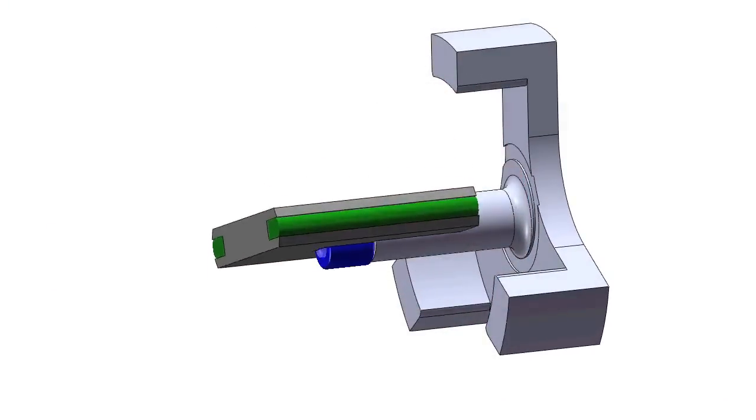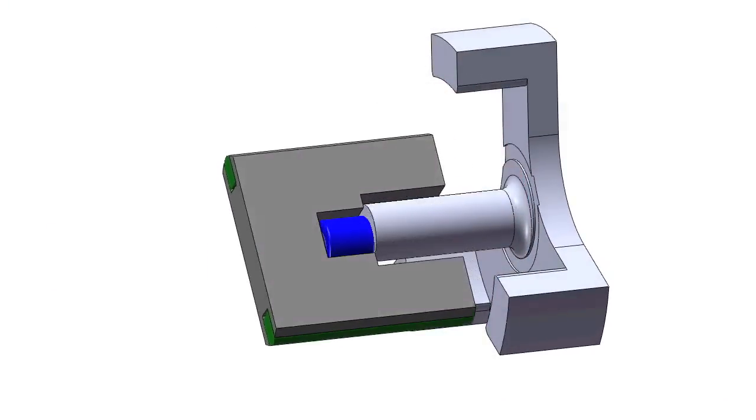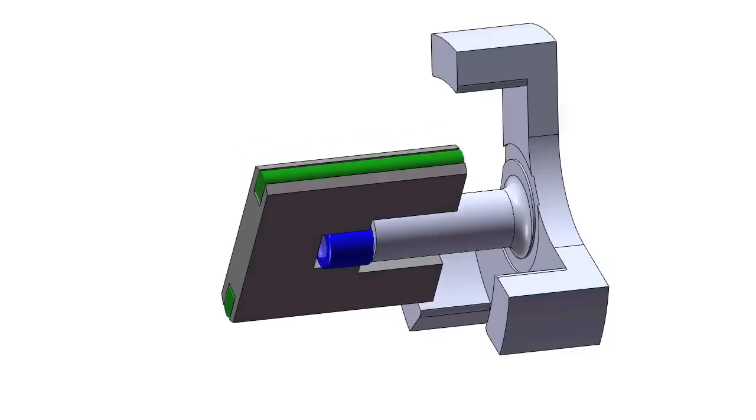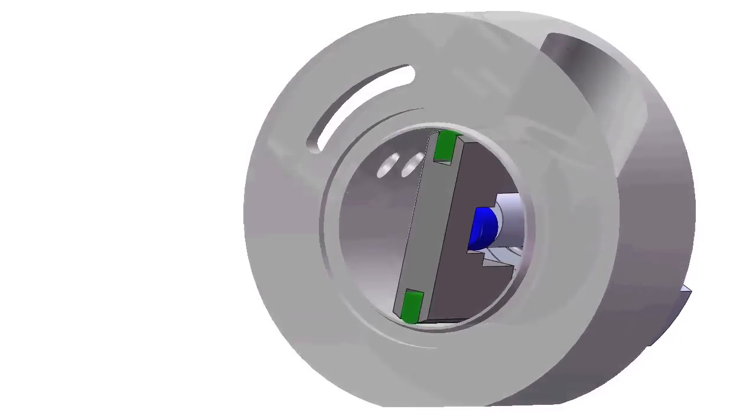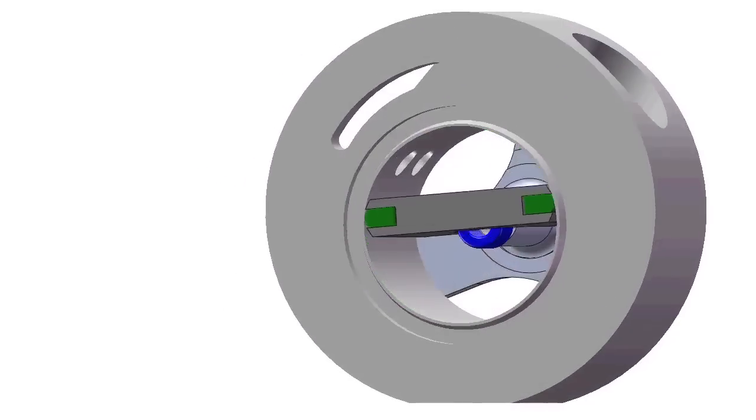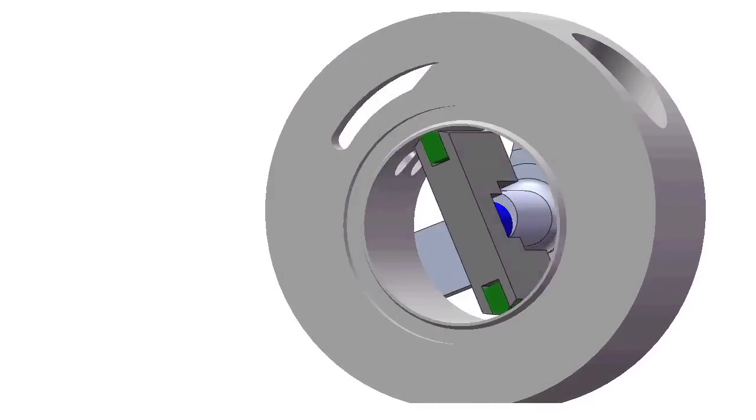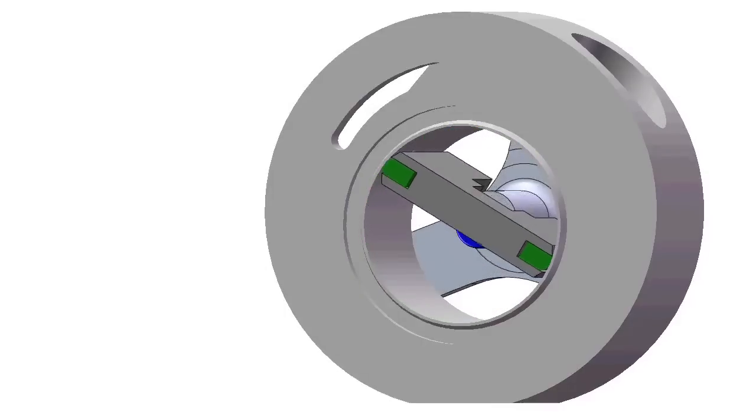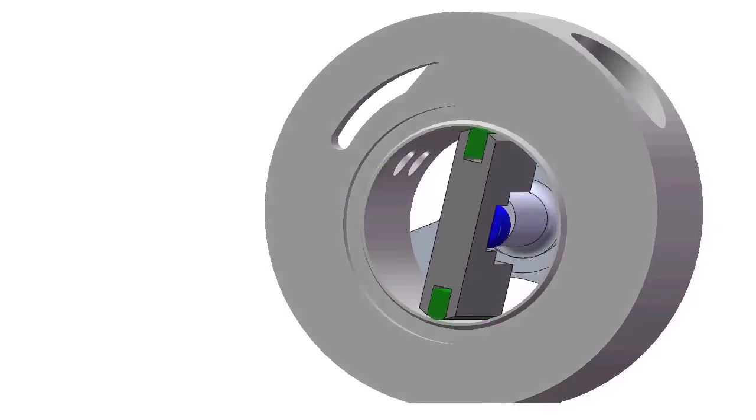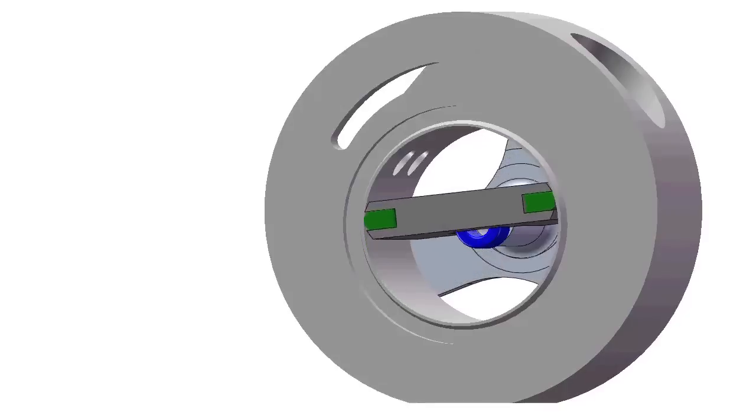Let's start with the Eccentric Cam, which is the heart of the compressor. The Eccentric Cam controls the rotating vane's position, maintaining the distal end of the vane at a very small, nearly constant distance from the housing bore. What would be sliding contact between the tip of the vane and the housing bore is replaced by rolling contact between the vane and the Eccentric Cam, resulting in very low friction and wear.